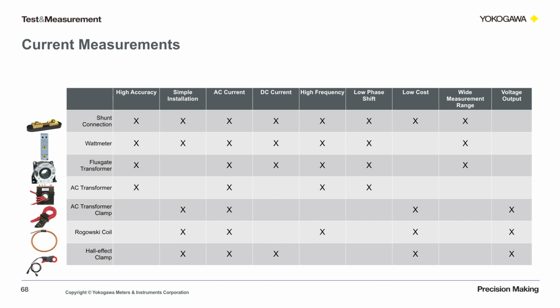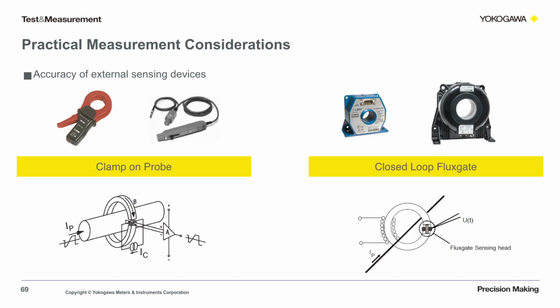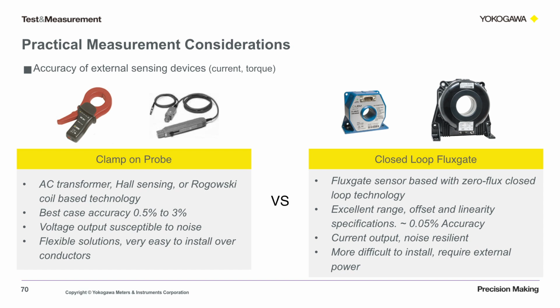Let's look at the clamp and flux gate in more detail. The biggest difference is that with the clamp-on probe you can open the core and place it around a conductor. On the closed-loop flux gate, you have to remove the conductor and place it through. The clamp-on probe uses a Hall effect sensor, and the closed-loop flux gate uses a flux gate sensor. To help quantify the trade-offs, accuracy is going to be the biggest consideration. The clamp-on is roughly 3% accurate, and the closed loop is about 0.05% accurate. The closed loop is more difficult to install, as we mentioned, but it's preferred for more permanent or semi-permanent test setups. The clamp-on probe is ideal for flexibility and quick answers, often used with oscilloscopes.